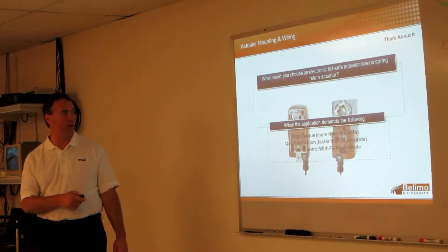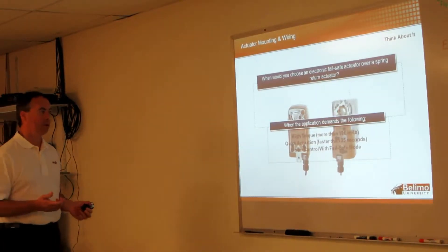If you need higher torque, I'm going to park this one down, Brian, since we go up to 270 inch-pounds now. But if you need a higher torque, more than 270 inch-pounds, we have an electronic fail-safe that goes to 360 without having to double up. Now our 270 inch-pounds, you can double those up to get extra torque as well if you want to stay with a mechanical spring.